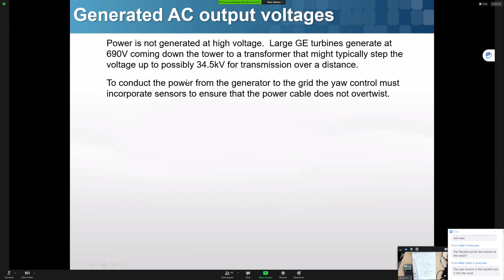Those conductors from the top of the nacelle go to the bottom using vertical cables. As the nacelle constantly turns to follow the wind direction, you need some kind of control to prevent over-twisting of those power cables. Some turbines have limit switches to control how many times the nacelle has turned, so if the cable becomes too tight, they automatically stop the turbine to unwind. Others have PLC counters that count the nacelle turning in one direction, how many turns. If it reaches the count set by the program, it will also unwind, turning in the backward direction to prevent over-twisting of the power cables.